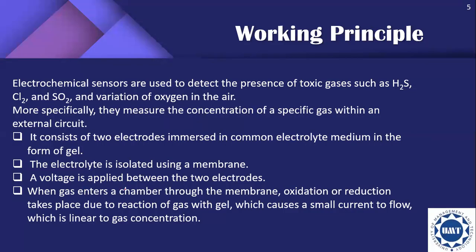A voltage is applied between the two electrodes through a battery. When gas enters the chamber, oxidation or reduction takes place due to the reaction of the gas with the gel, which causes a small current to flow that is directly proportional to gas concentration.